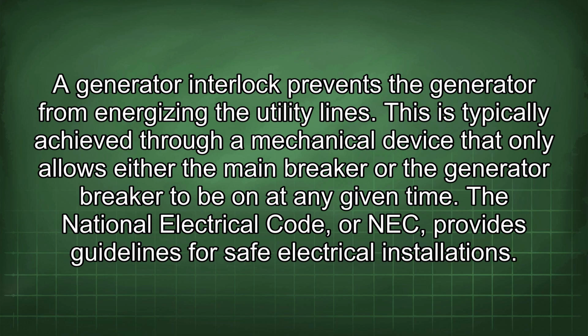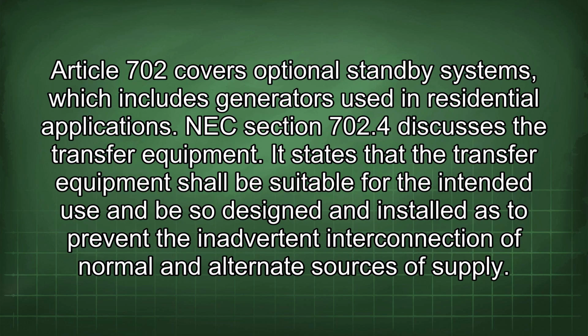The National Electrical Code, or NEC, provides guidelines for safe electrical installations. Article 702 covers optional standby systems, which includes generators used in residential applications. NEC Section 702.4 discusses the transfer equipment. It states that the transfer equipment shall be suitable for the intended use and be so designed and installed as to prevent the inadvertent interconnection of normal and alternate sources of supply.